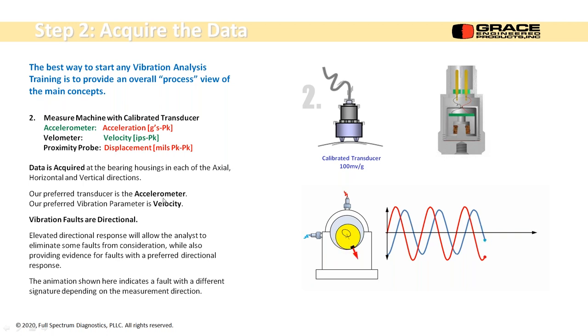Our preferred transducer is an accelerometer. Our preferred vibration parameter is velocity. And we have to remember, vibration faults are directional. I'm showing you two transducers, one vertical and one horizontal. The unbalanced vector is sweeping by and it peaks out as it goes by the red transducer on the red curve here. And 90 degrees later, the blue one's going to peak out. So what does this mean?